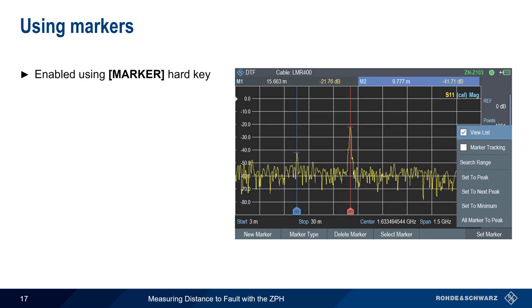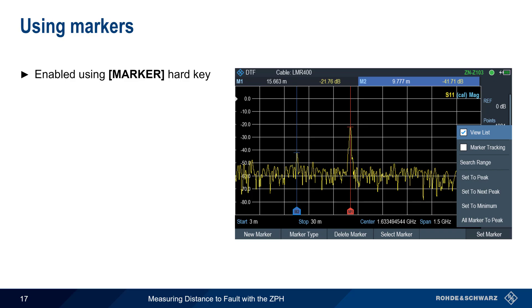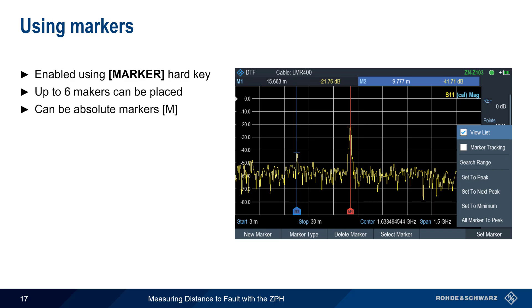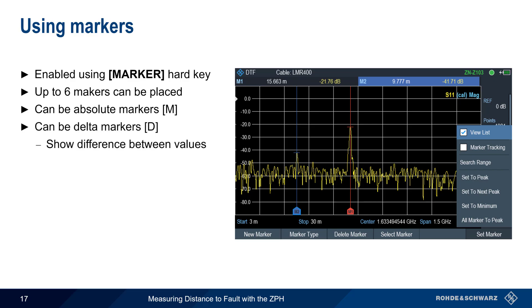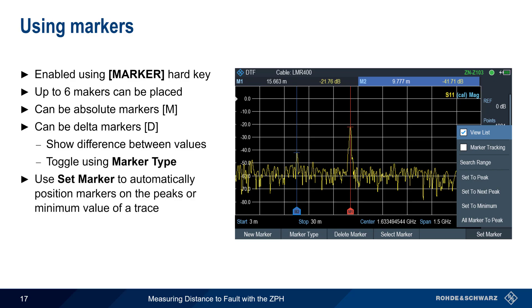Markers are enabled using the Marker hard key, and these can be used to numerically quantify DTF faults or events. Up to six markers can be placed on a trace, and these can be either absolute markers or delta markers, which show the difference between marker values. You can toggle between types using Marker Type. The functions provided under Set Marker can be used to automatically place markers on peak or minimum values of the displayed trace.